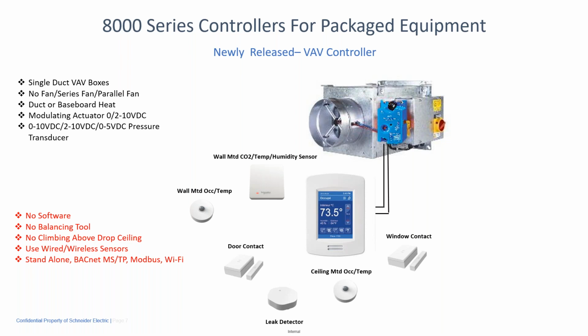Again, you can incorporate the wireless sensors as well, temperature and humidity, CO2, occupancy sensors, door and window contacts, and leak detectors. And the cool part about this, in order to configure it, you don't need any software. There's no balancing tools. You do all the balancing from the face of the controller. So you don't have to climb above a ceiling level or get on a ladder to be able to connect to a controller. You do it all from the touchscreen interface, right?